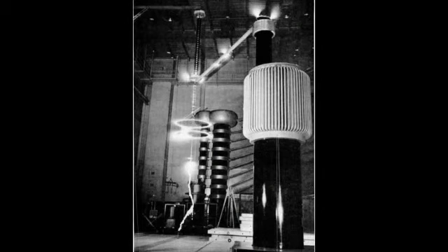Corona discharge usually forms at highly curved regions on electrodes, such as sharp corners, projecting points, edges of metal surfaces, or small diameter wires. The high curvature causes a high potential gradient at these locations, so that the air breaks down and forms plasma there first. In order to suppress corona formation, terminals on high-voltage equipment are frequently designed with smooth large-diameter rounded shapes like balls or toruses, and corona rings are often added to insulators of high-voltage transmission lines.